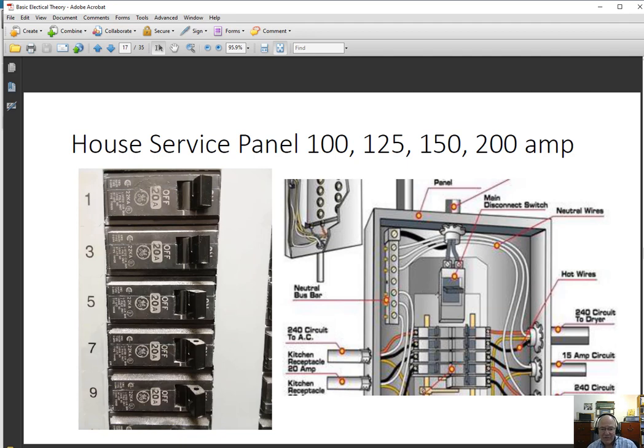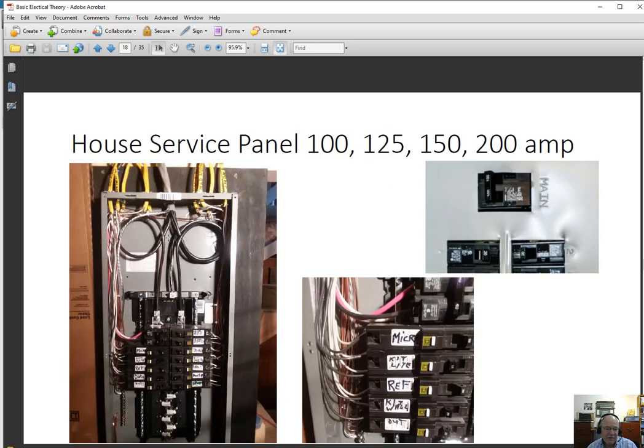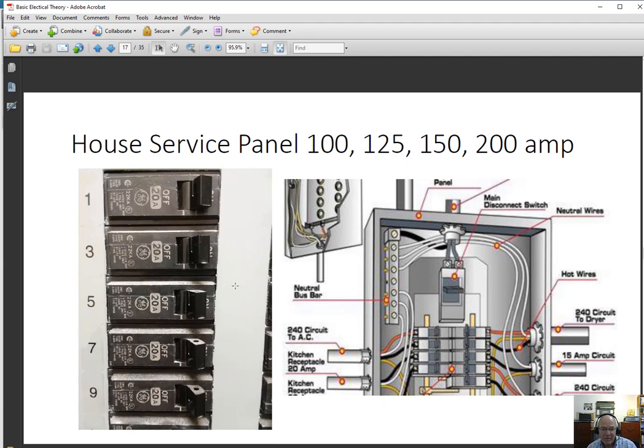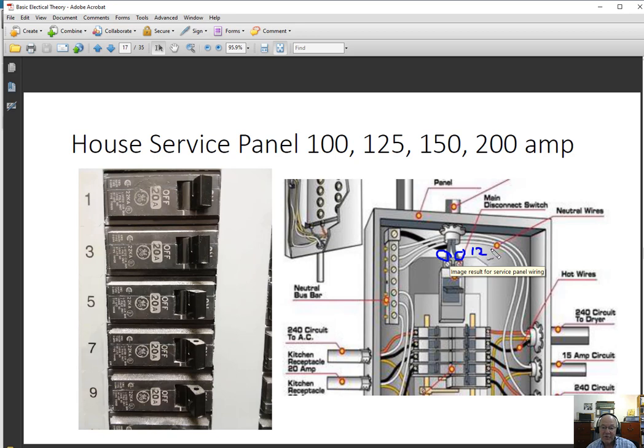When you have the service panel, there are two sides. The row on the left is odd numbers; the row on the right is even numbers. Those numbers simply identify individual circuits. Looking at the schematic, coming into your home are two hot wires. Those hot wires are called hot because current is flowing through them. You also have a neutral and a ground. They go to two opposite sides of the service panel — one goes to the left, one goes to the right. Each wire is carrying 120 volts; since they're both 120 volts, that gives you 240 volts total if combined together.